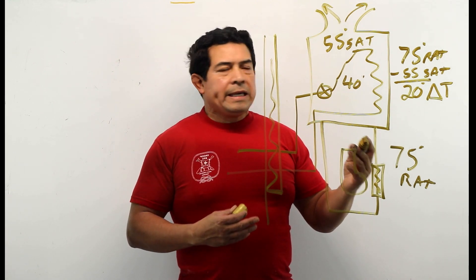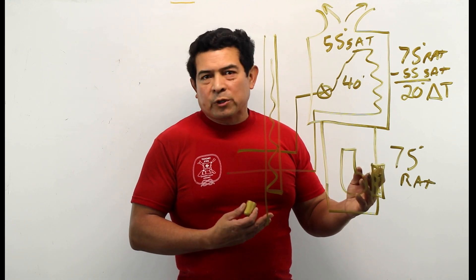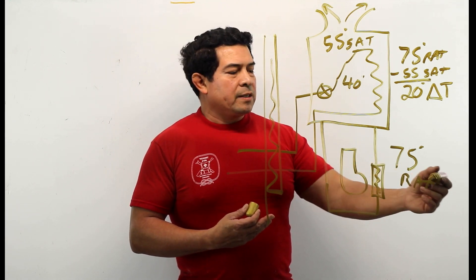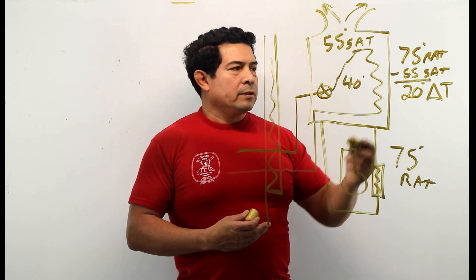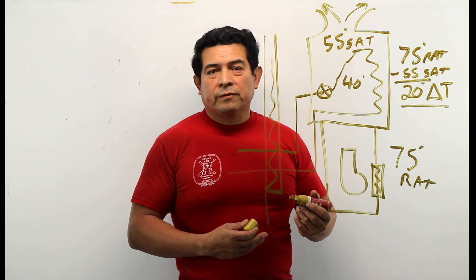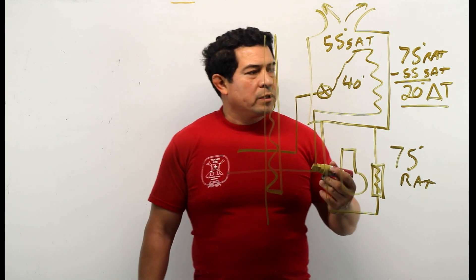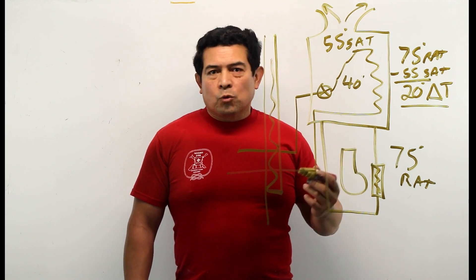When you say 20 degree delta T, delta T is just a fancy way of saying temperature difference. So we see that we have 75 coming in here, 55 going out. When we subtract we have 20 degree temperature difference, or in other words 20 degrees delta T if everything is working right.